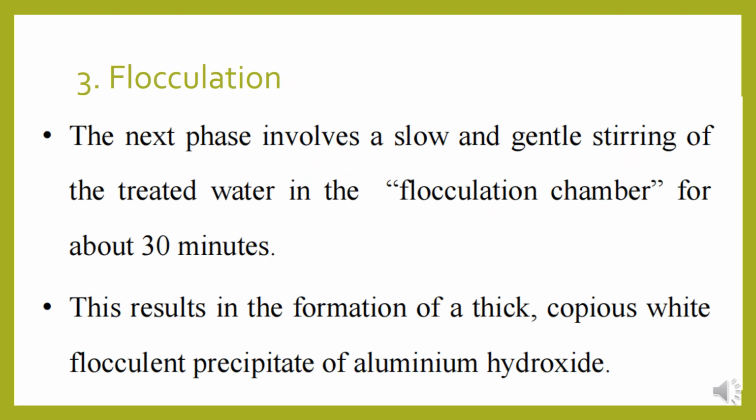Third step is flocculation. The next phase involves a slow and gentle stirring of the treated water in the flocculation chamber for about 30 minutes. This results in the formation of a thick, copious white flocculent precipitate of aluminium hydroxide.